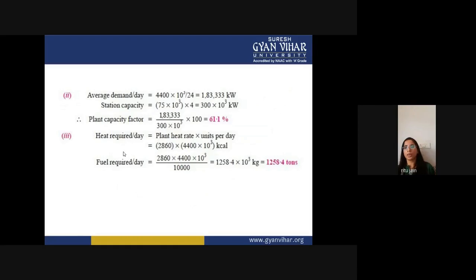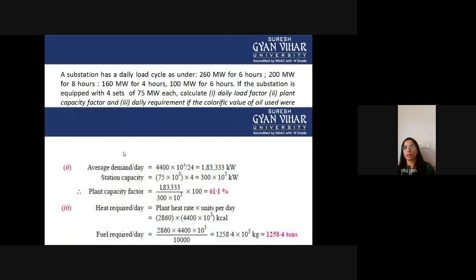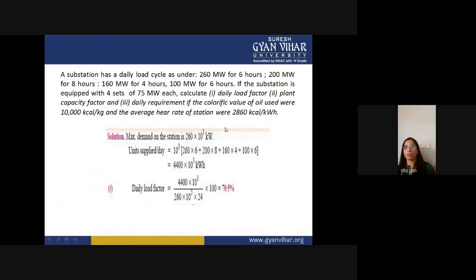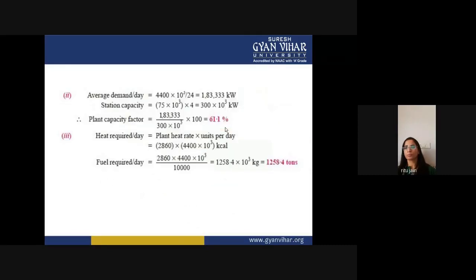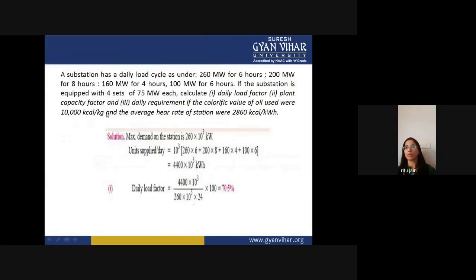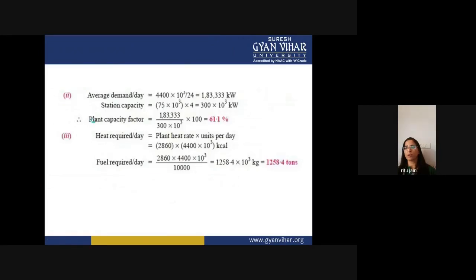Now, the next point is the heat required per day. The calorific value is also given. So heat required per day is equal to 2860 into 4,400 into 10 to the power 3, which is the average load, and 2860 is the plant heat rate. This is the heat required, in kilocalorie. And if you want to calculate the fuel, you have to divide this heat by 10,000 kilocalorie per kilogram, the calorific value of this fuel, and you will get the fuel required in kilogram.